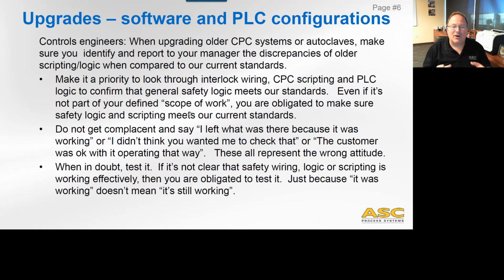And even if it's not part of your defined scope of work, even if you're there doing something else like adding some vacuum valves to an existing autoclave, you are obligated to look through those safety elements and make sure that they are up to snuff, okay? And if they're not up to snuff, come up with a corrective action with your manager on how we're gonna make that change, okay? And what we'll do at that point is decide whether that existing safety logic and existing safety interlocks are safe enough to meet the future of that equipment, okay?